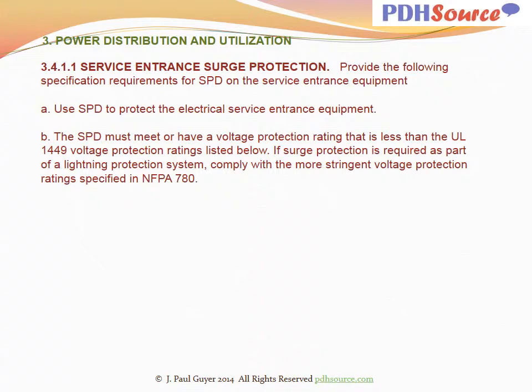With regard to service entrance surge protection devices, provide the following specification requirements for surge protection devices on the service entrance equipment. Use SPD to protect the electrical service entrance equipment. The SPD must meet or have a voltage protection rating that is less than the UL1449 voltage protection ratings listed below.